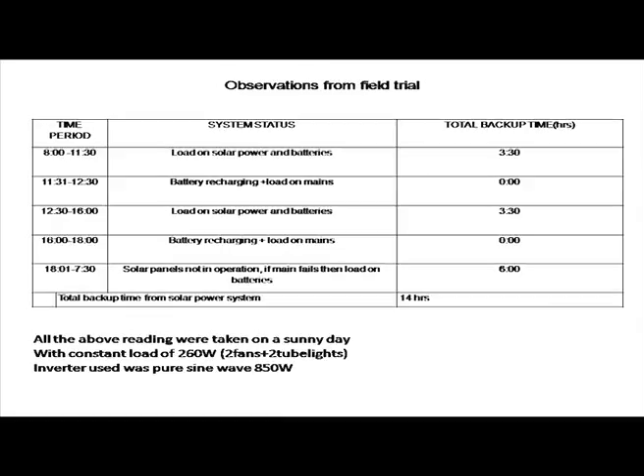These are the observations from one day of field trial of our system. From 8 am to 11:30, we have our load powered from solar energy and batteries. Further taking more readings, we reached to total backup time of 14 hours. All the above readings were taken on constant load of two fans and two tube lights which adds up to 260 watts.